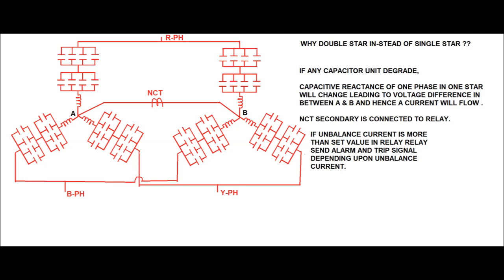Why is double star connection used for the capacitor bank instead of single star? If a single star connection is used, there is no possibility to detect a faulty unit in the capacitor bank. In the double star connection, two star points are formed, and between the two star points a neutral CT is connected.